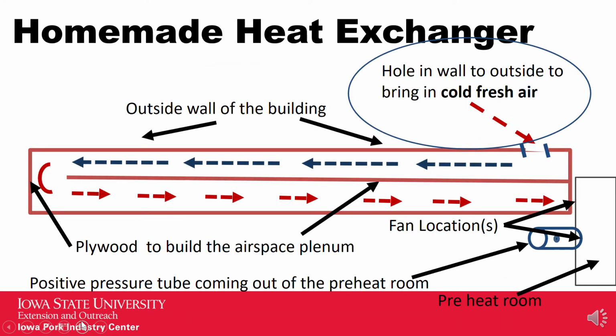So here I'm going to go through the schematic of the homemade heat exchanger. Here you can see the outside of the building, pointed to by the arrows, and the box to be built along the ceiling. In the center of the box, you build a divider to force the air down the length of the building and return. Cut a hole in the wall so that fresh outside air can enter the building. You may want to put a fan here to push the fresh, cooler air inside the plenum. The airflow will travel the length of the building and back to the end of the plenum.